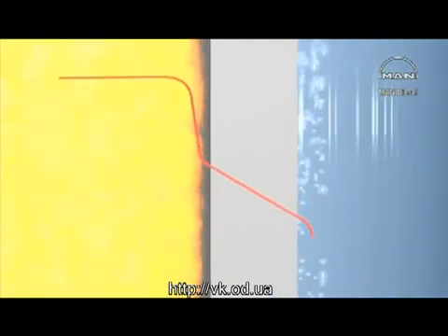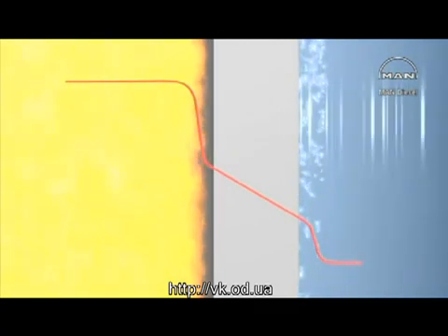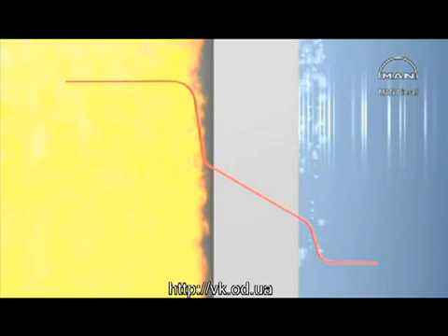The high wall temperature causes a local boiling, which is able to absorb relatively large amounts of heat. Small steam bubbles are formed, which immediately break loose from the surface and condense in the surrounding water. Due to this, the wall temperature is almost independent of the transmitted amount of heat, provided that the water temperature is safely below its boiling point.